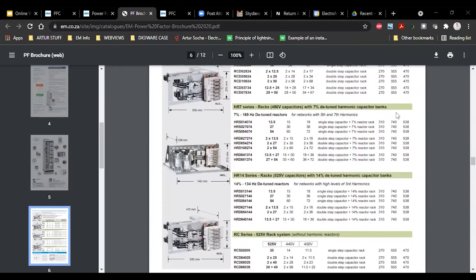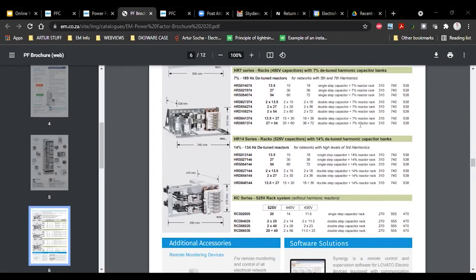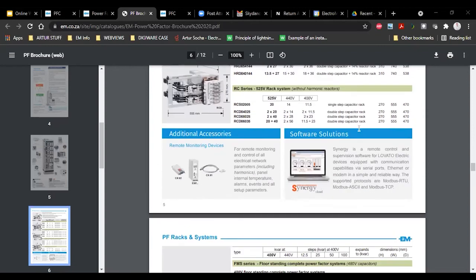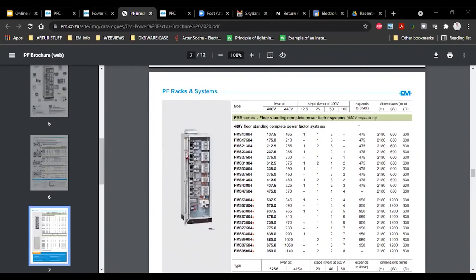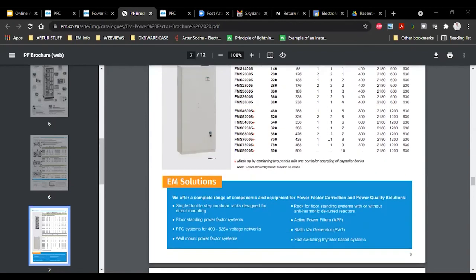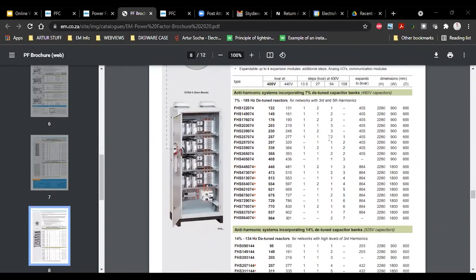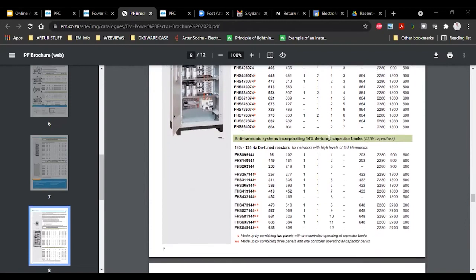Then we do what we call detuned reactor based. As before, that line reactor is wired in series with the cap to protect the caps. Depending on your network harmonics, if you've got high levels of 5th and 7th, which is what we typically see, you would go for what we call a 7% detuned capacitor bank. If you had high third orders, you'd go for 14%. This is just some examples of the floor standings that we build. We try and keep to the step configuration, but we can obviously build much bigger systems for you. You will get this brochure, so you can go through it in your own time.